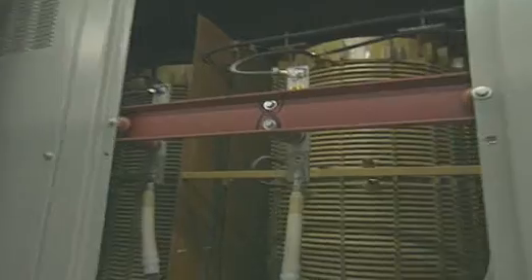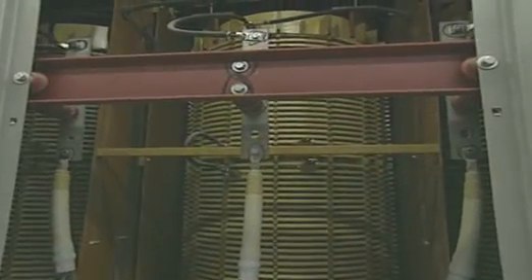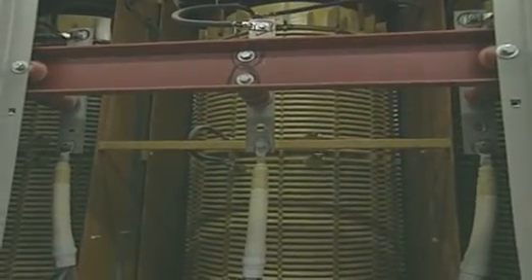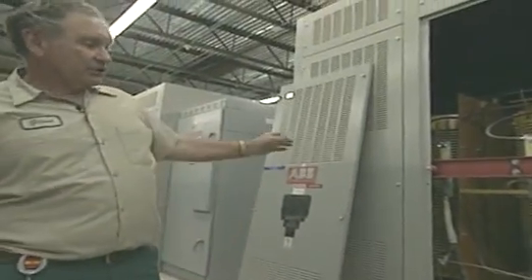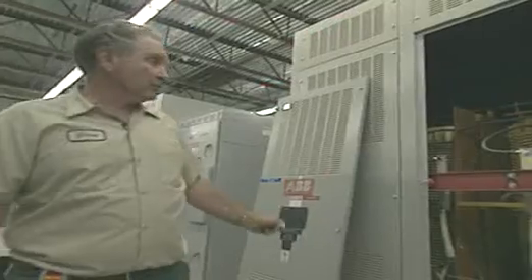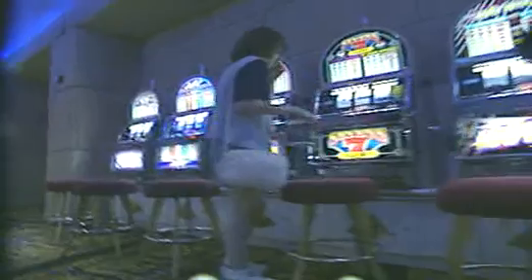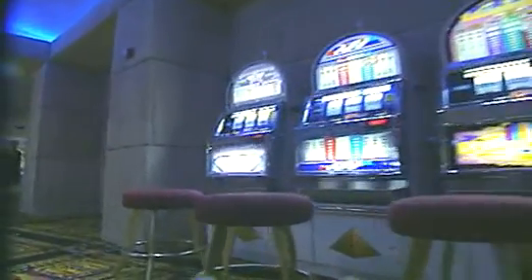The Luxor Hotel needs its own bank of transformers to step the high voltage alternating current down to various voltages. You're seeing three big coils in there. That reduces the 12,400 volts down to 4,160 volts. This is the power that we use for our air conditioning units. And then it goes to another bank of transformers that breaks it down to 120/208 volts that we use for lighting and for slot machines, gaming, and whatever else it might be.